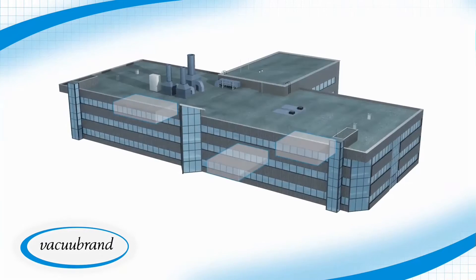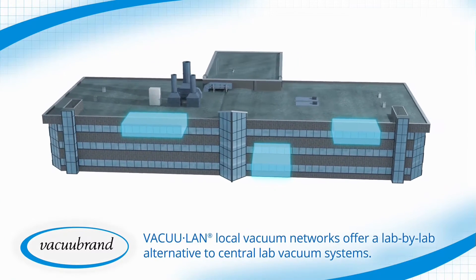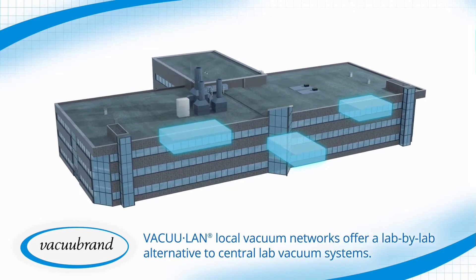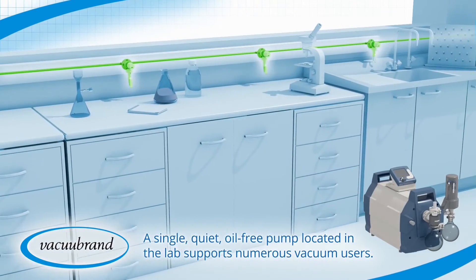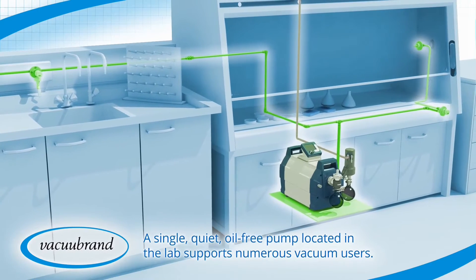VACUU·LAN local vacuum networks provide a lab-by-lab alternative to central lab vacuum systems for both new and renovated laboratory spaces. A single quiet oil-free pump in the lab supports numerous vacuum users at benches, fume hoods, and biosafety cabinets.